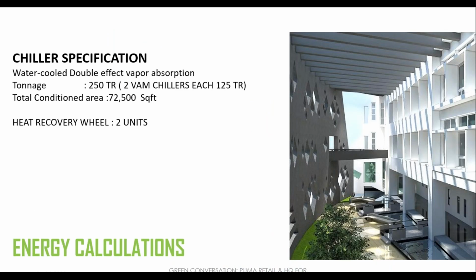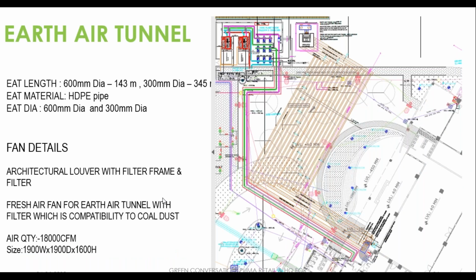Initially, the earth air tunnel was supposed to feed not just the ground floor naturally cooled areas, like the cafeteria and library, but was also supposed to provide fresh air for all the AHUs on the upper floors—first, second, third, and fourth. But then it evolved, and they did not want to do the earth air tunnel to that extent. So now the EAT is restricted to the entire ground floor, and for the upper floors we've introduced a heat recovery wheel with the VAM chiller.